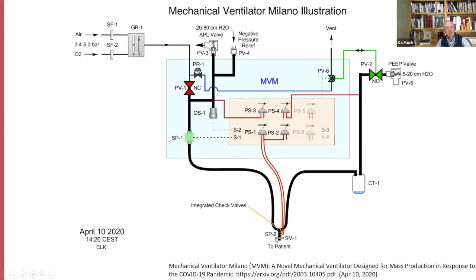There's an antimicrobial filter here. There are check valves here, unidirectional valves, to make sure that gas is really only going in one direction. The patient inhales or gets ventilated, and then on exhalation, gas goes back out. Here's a water trap so that you can collect water, and then there's a simple on-off type exhalation valve. This one is actually pneumatically controlled. There's a membrane pneumatically controlled exhalation valve, and that valve is controlled by a pneumatic solenoid here. And then here's your PEEP valve, and then it goes out.